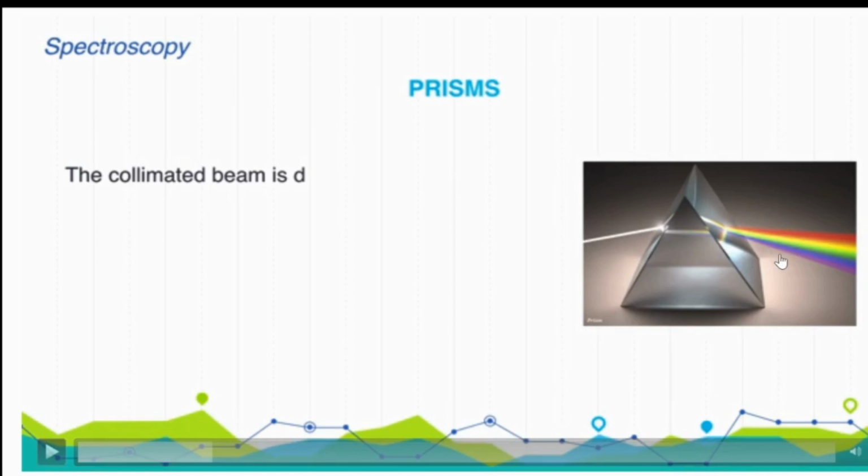The separation is happening here. If this separation does not happen, we won't get an accurate result at the end of the experiment. So that is the purpose. This beam is polychromatic, meaning it contains different wavelengths. So we need to separate it into its constituent wavelengths, separate wavelengths, and then select one wavelength. That's the purpose of the monochromator.